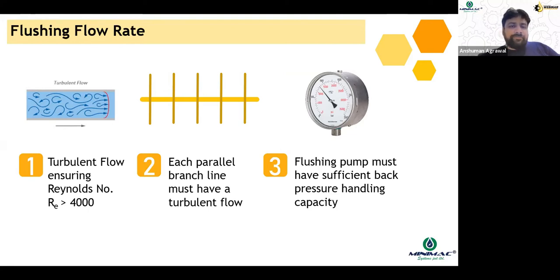Because probably if you design the flow rate based on the largest diameter pipeline, what happens when this flow rate gets distributed in around 10 different branches? It gets divided. And when it gets divided, probably you would not get the desired flow rate in the branch lines. So instead of deciding the flow rate across the largest diameter pipeline, you must decide the flow rate across each of the branch lines.